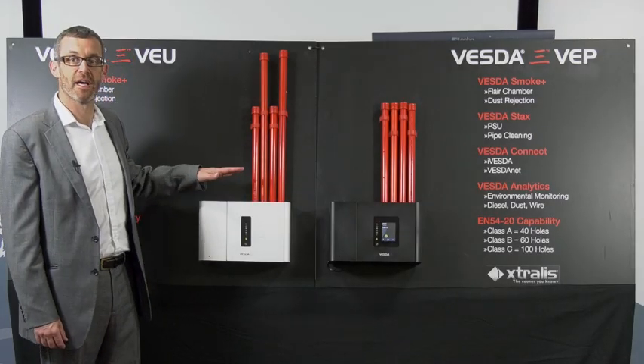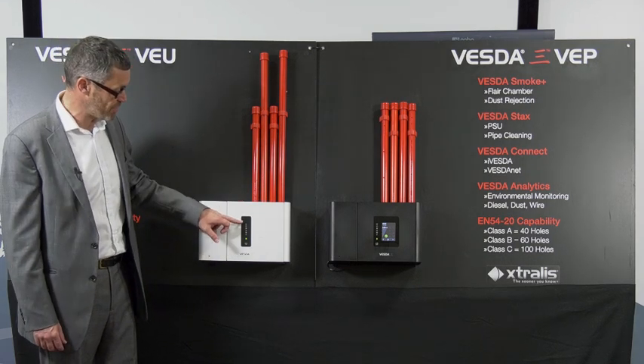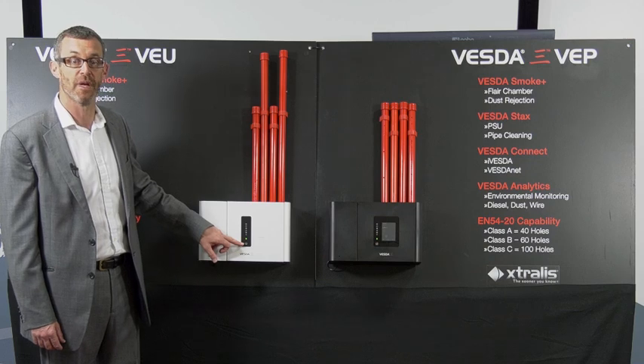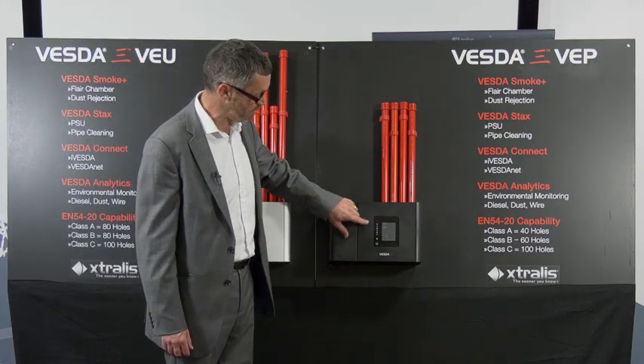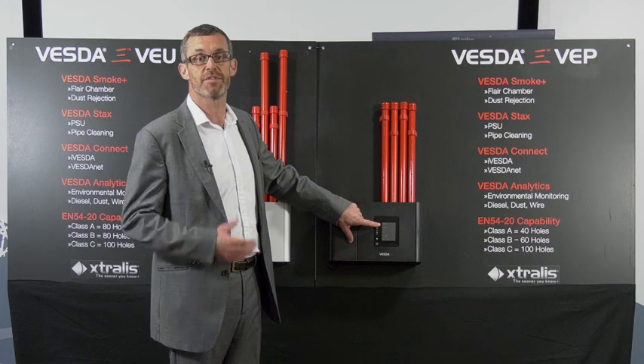Across the VESDA-E range — the VEU, VEP, and VEA — we can have either a basic LED display which shows the four fire outputs, a fault condition, and whether the unit is isolated, with a reset and isolate button on the front; or we can have the full three and a half inch touchscreen display which still includes the LEDs but also provides a touchscreen interface giving us a lot more information.